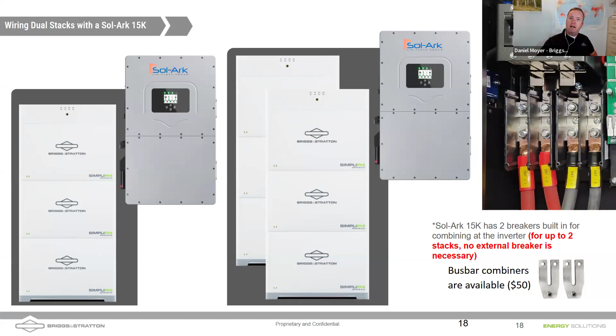I'd always recommend 2 parallel sets of wire, just like is shown in the picture there. One thing with those Y bus bars: I've seen photo evidence of the conductors heating up because people unfortunately did not size their conductors large enough. Not all 4-aught wire, which is typically what would be used with those Y bus bars, will be rated for a continuous 275 amps for the 15K, for example. So the conductors can get too hot. I've seen melting around those terminals, or the weak point may be where they're lugged on. So I would definitely say proceed with caution.